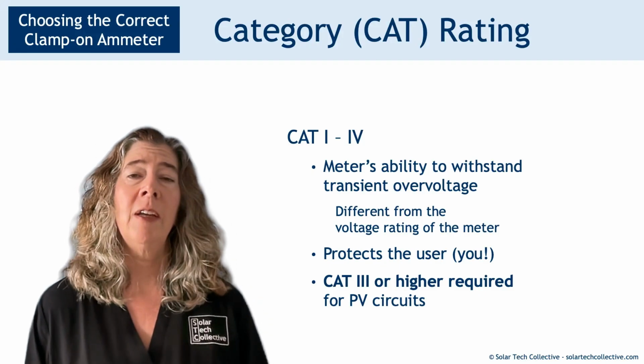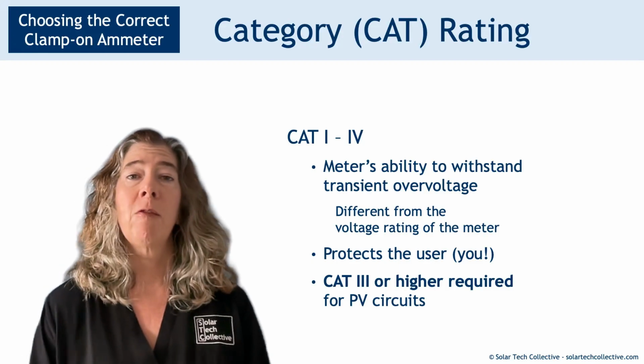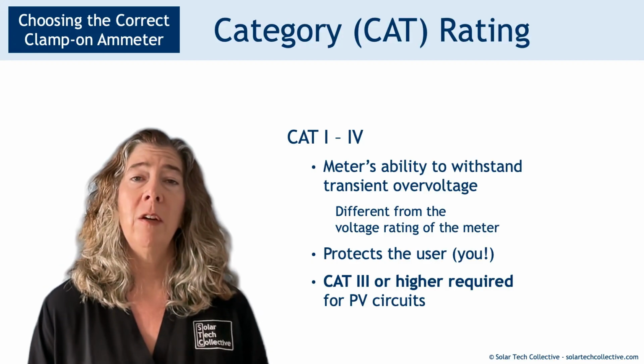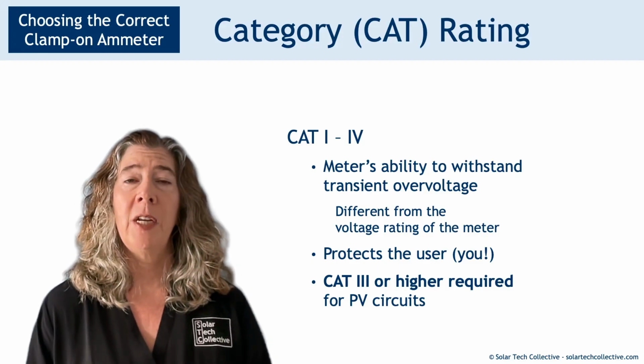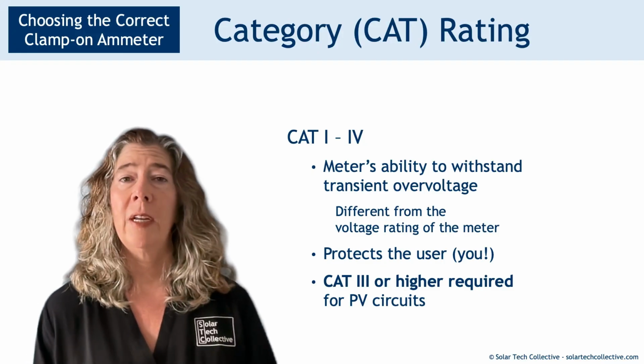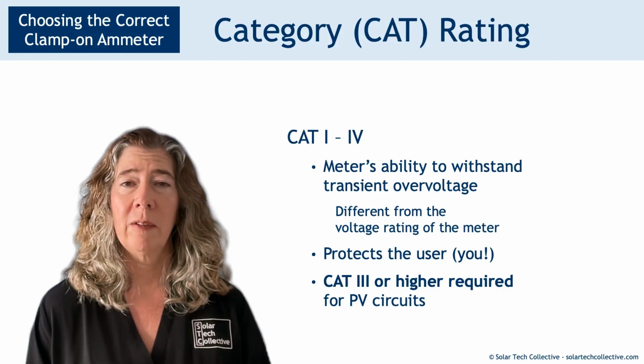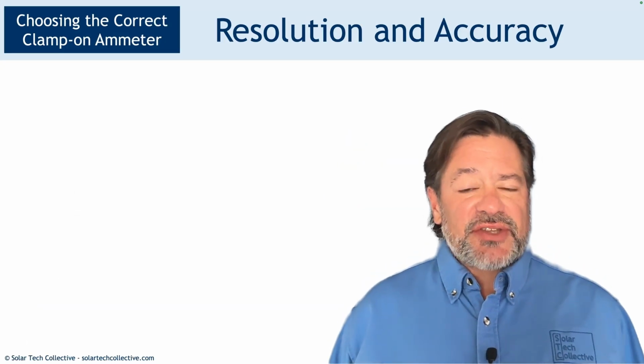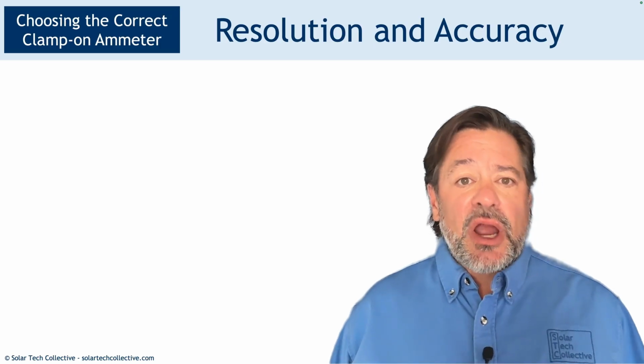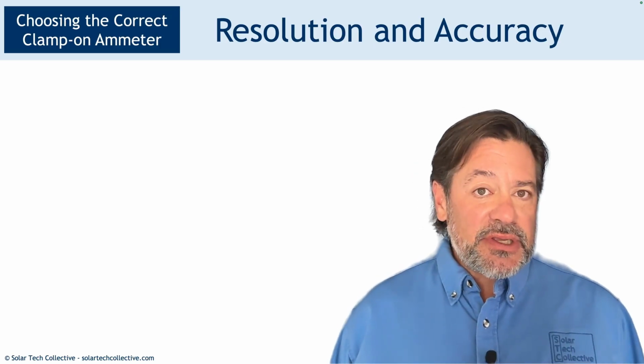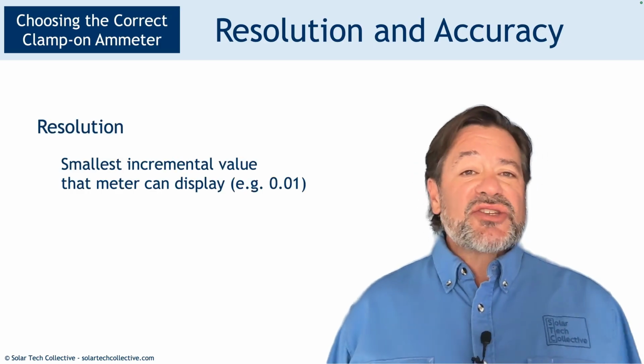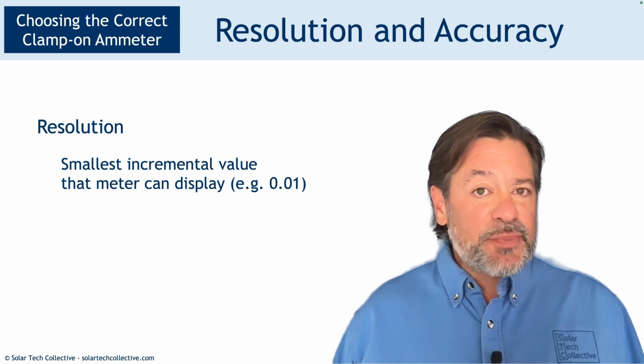And just to mention, this is different than the voltage range rating of your meter. It is a separate rating on the meter, and it is not directly correlated with the voltage range. Two other key characteristics to consider when selecting a clamp-on ammeter are resolution and accuracy. Resolution is the smallest incremental value that the meter can display.